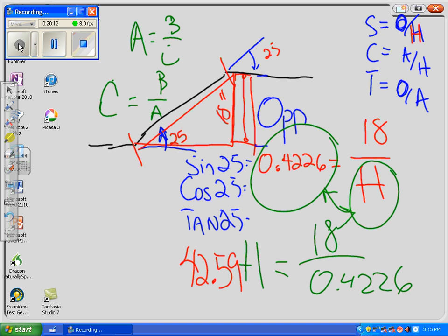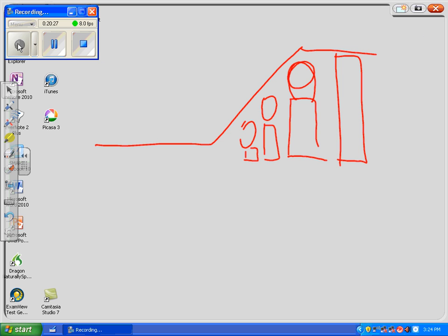Okay, so now we have the basic idea of bending pipe and how we use this triangle thing, right? Let's do that again. Now we're going to look at this from a different point of view. We're going to look at this as a conduit bending exercise, but this time we're going to ask what angle we need to use. Because there are going to be times when there are things in the way. Let's say there is a rack of I-beams that are cut to let a piece of conduit sit on top of them, and they're running across your path. So they're totally in the way.